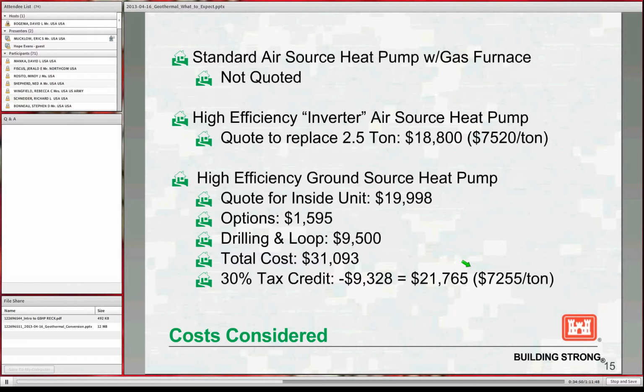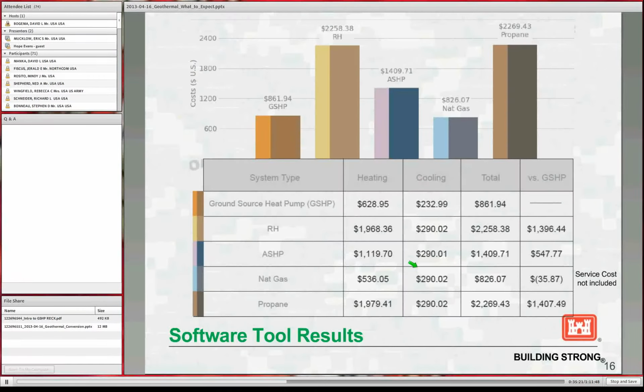And if you look at that in terms of the per ton difference, it's actually cheaper. Although you could argue that I didn't necessarily need the additional tonnage, but also the $21,000 included some other benefits that the variable speed model of the geothermal system had for humidity management. It has things where it runs the fan and compressor at a very low speed to prevent the air from drying out as much as the typical on-off cycle of a dual speed or full speed system.